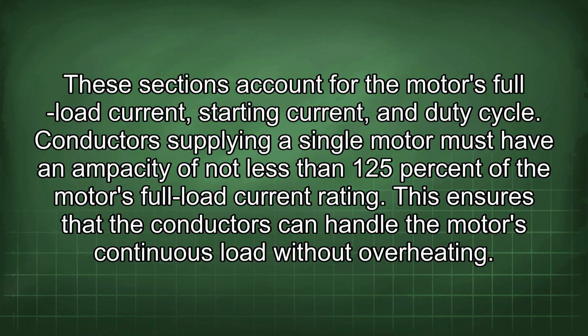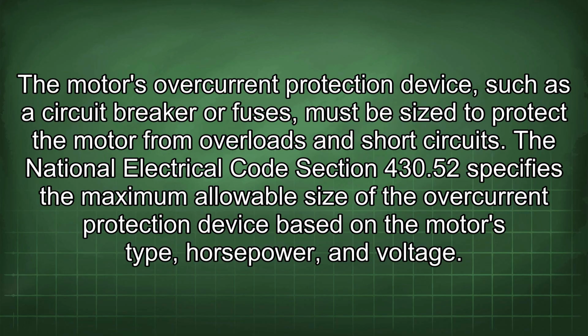This ensures that the conductors can handle the motor's continuous load without overheating. The motor's overcurrent protection device, such as a circuit breaker or fuses, must be sized to protect the motor from overloads and short circuits. The National Electrical Code Section 430.52 specifies the maximum allowable size of the overcurrent protection device based on the motor's type, horsepower, and voltage.